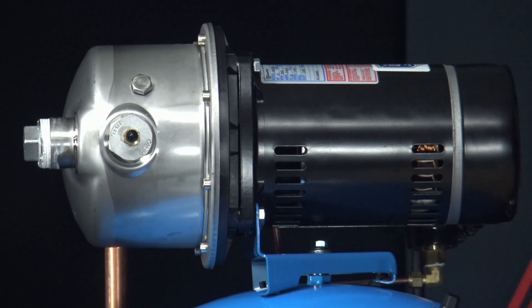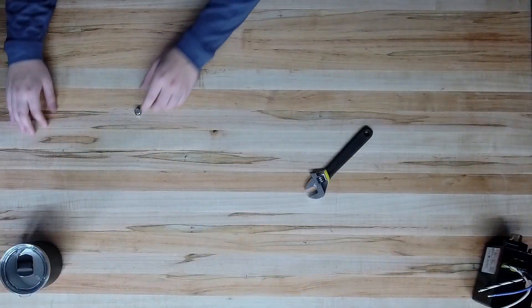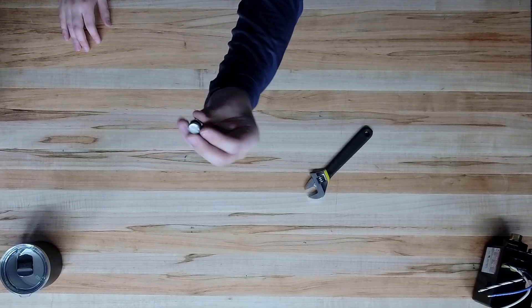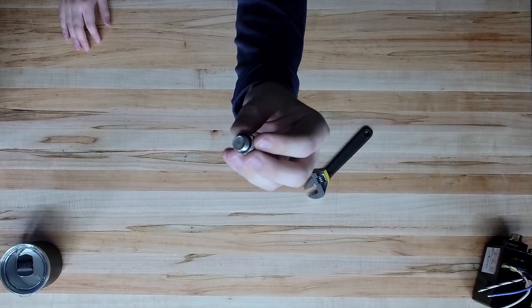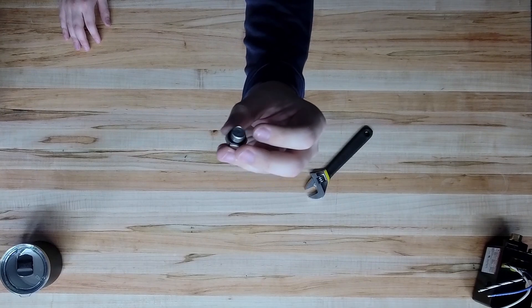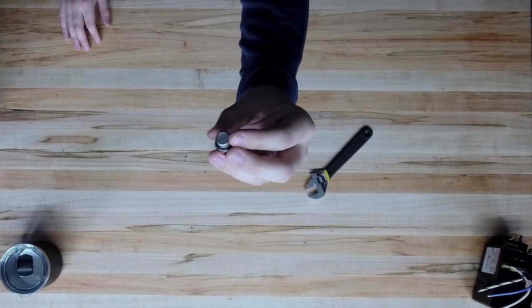Now that half turn is pretty important, there's a reason for that. So this screw is actually pretty small, it's only one and a half threads. The reason why we only want to turn it one half turn is because we don't want it to come out of the housing of the pump.